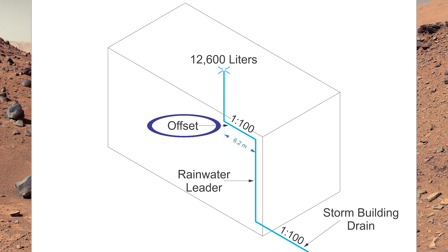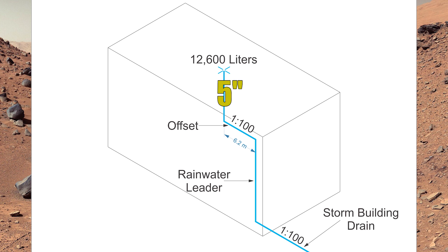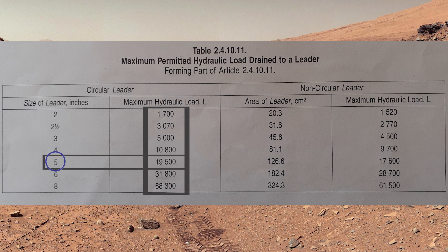So we need to size this section as a storm building drain. This is a 15 meter by 30 meter roof with a liter load of 12,600 liters of rainfall going through the roof drain. That first section of rainwater leader before it gets to the offset can still be five inches in size. We can tell that by looking at table 241011 — going across at 19,500, it says we can be five inch.